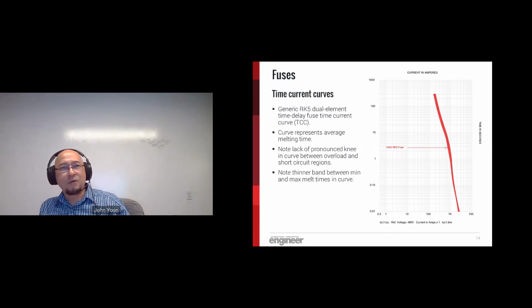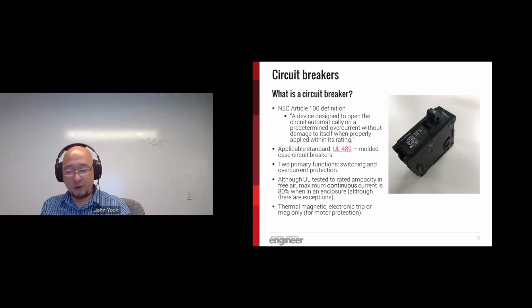So you can see that that thin red band has some width to it. This is due to manufacturing tolerances. So the fuse is guaranteed to open somewhere within that band, not necessarily at an exact number, but somewhere in that band. You can also see, if you follow the graph up the time scale towards the top at the 200 second mark and cross-reference that with current, that the fuse actually holds substantially more current than 100 amps for that period of time. Before we leave this slide, let's take a look at the bottom of this curve. You can see where we have a very high magnitude of current, how that fuse reacts in a fault condition. This will become more important when we're comparing these to circuit breakers.